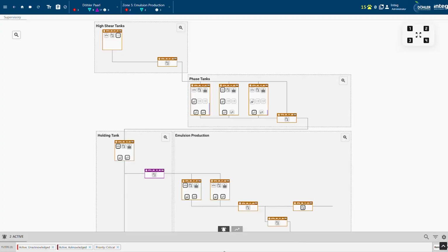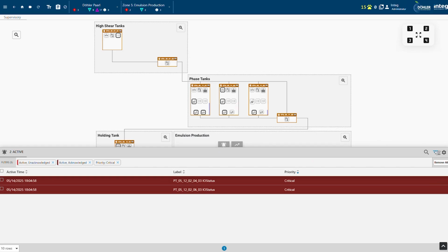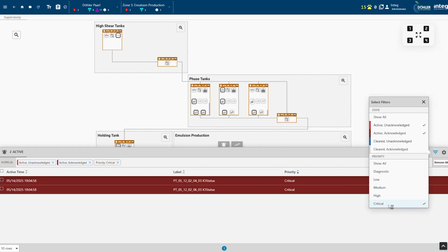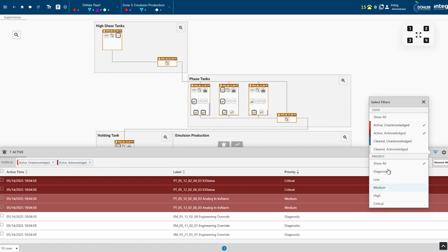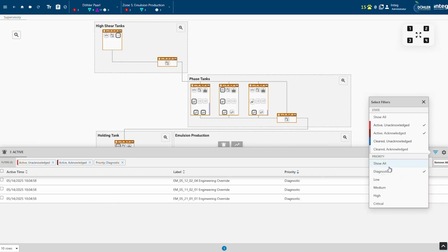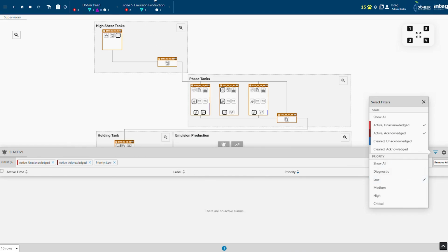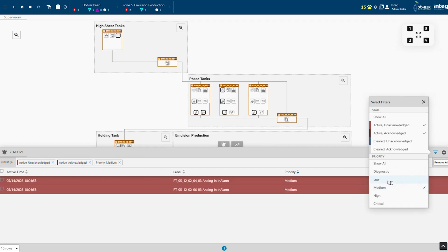We developed the breadcrumb system to display the number of alarms depending on their severity, filtering them down to the specific area or process cell. It aids the operator to identify problem areas within the plant and quickly navigate to them using the alarming module within Ignition. We integrated this alarming system with the breadcrumb system to allow maintenance to pinpoint problems down to the control module level.